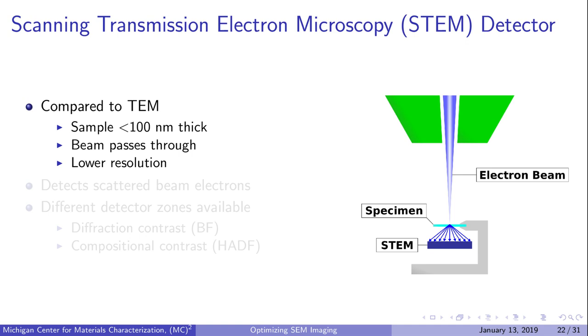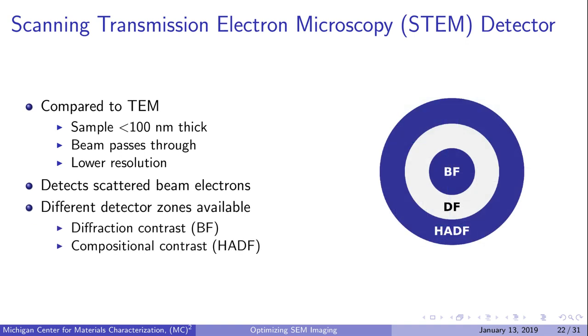Last but not least, we have the STEM detector. STEM in an SEM is similar to TEM in that samples have to be thin—usually less than 100 nanometers—and the beam passes through the sample. Due to voltage limitations, STEM in an SEM is often lower resolution compared to TEM, though it is capable of resolving nanometer-scale features. The STEM detector uses scattered electrons to generate an image. Most STEM detectors are divided into concentric segments: the center segment is bright field, which detects electrons scattered the least and shows the most diffraction contrast. The middle zone is dark field, and the outer zone is high angle dark field. Heavier elements scatter electrons to a higher angle, so the high angle dark field zone provides the most compositional contrast.